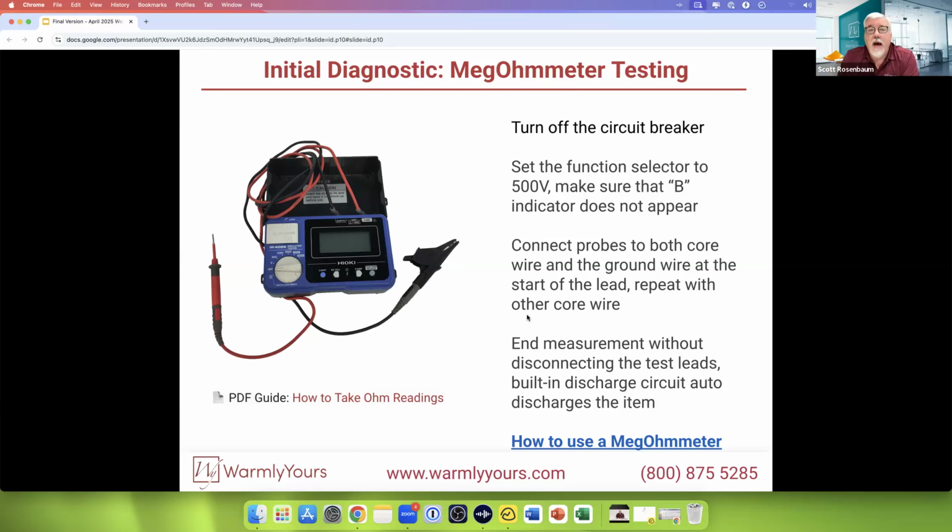especially in bathrooms. If they have an exhaust fan, you turn the exhaust fan on and all of a sudden the floor GFIs. That tells you it's not the floor. It tells you that the power getting to the floor, there's something going on with it. So if you don't get a result from the digital ohm meter first, and it says it's okay, then do the megohm meter.